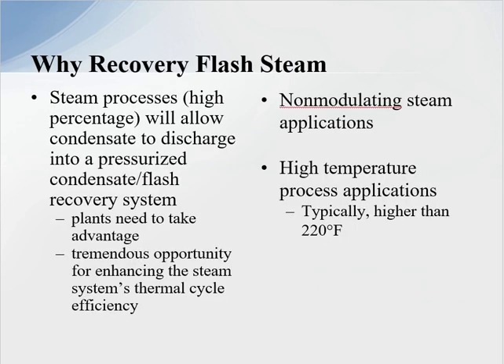Why recover flash steam? Steam processes at high pressure with a high percentage of flash will allow condensate to discharge into a pressurized condensate flash recovery system. Plants need to take advantage of this — as you saw in the previous slide, the large volume of flash steam is a tremendous opportunity for enhancing the steam system thermal cycle efficiency. We talk about two systems in plant operation: non-modulating steam applications, and high temperature process applications where we can utilize cascade systems and thermal compressing systems.